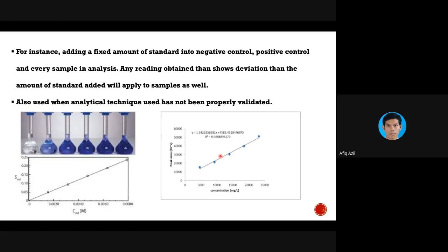For pharmaceutical analysis, the acceptable R squared value is 0.99xx. That means you can start from 0.9901 until the maximum of 1.0. The best is to get 1.0, but that is very hard. If you can get 0.9975, for example, that is good enough. Then only can the standard be used together with the sample.